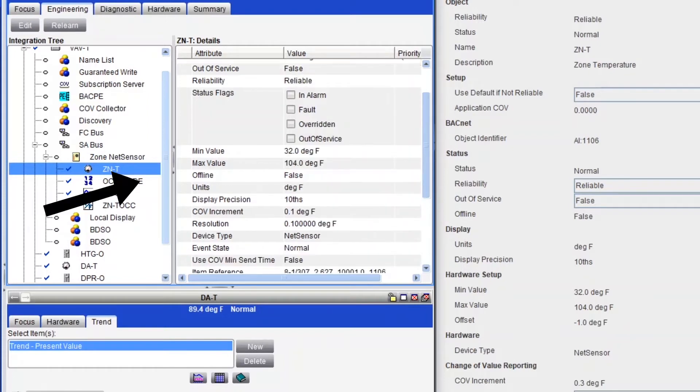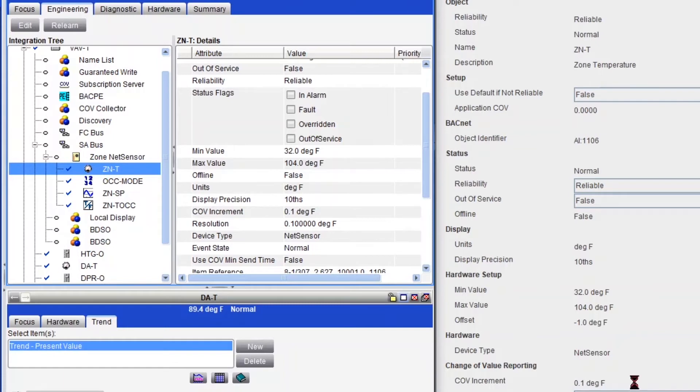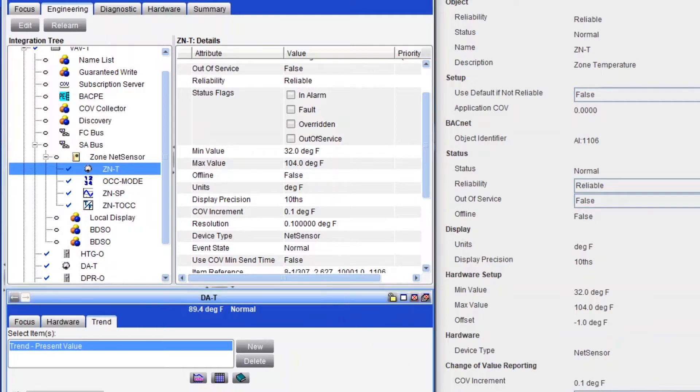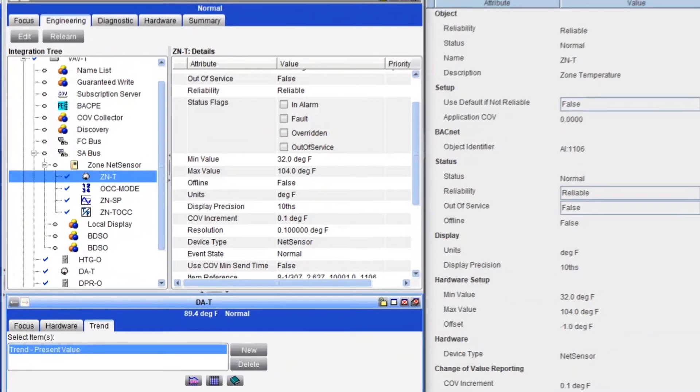And we should see the update right here. There you go. And I think all temperature points are set to 0.3 increments by default, which is all right. But if you want to calibrate your room temperature sensor, it's better to have them at 0.1.